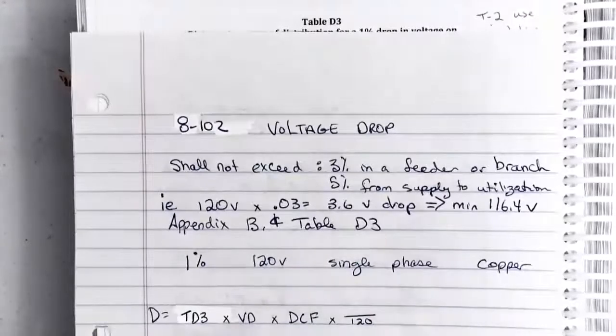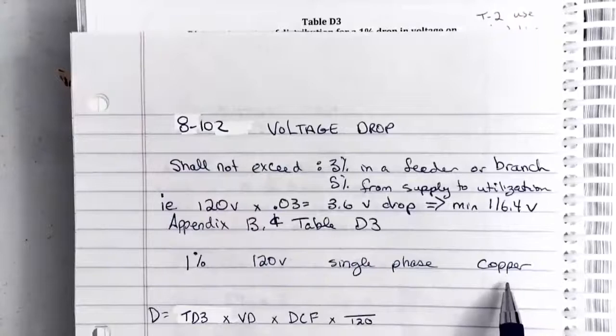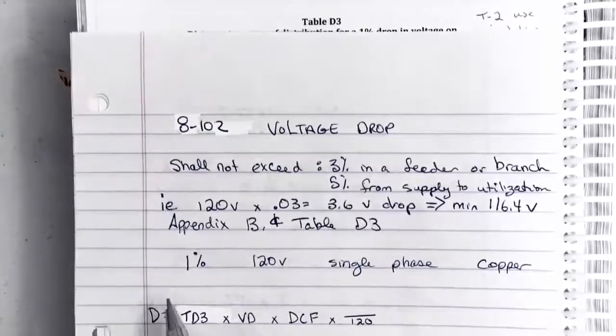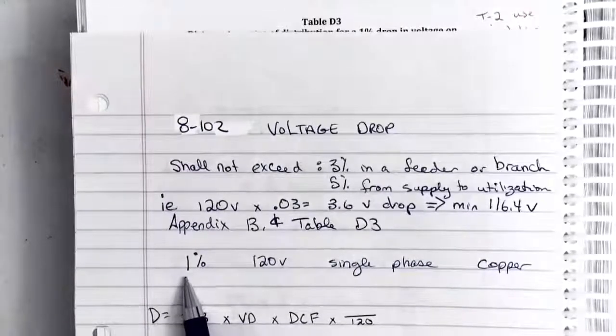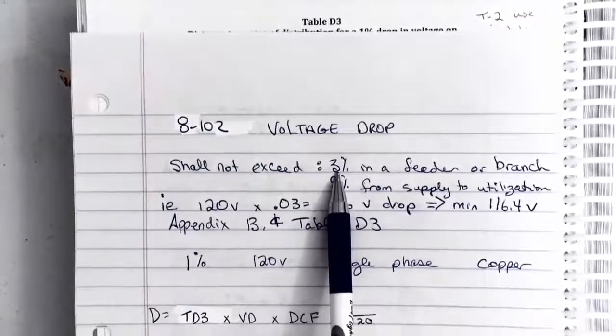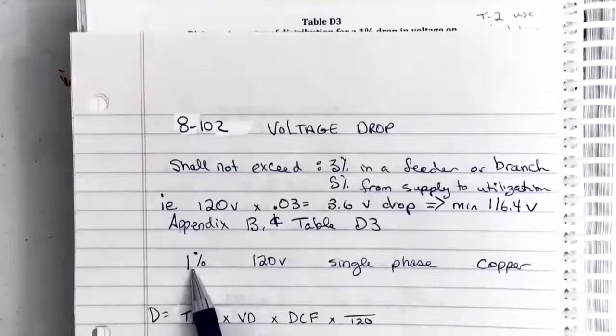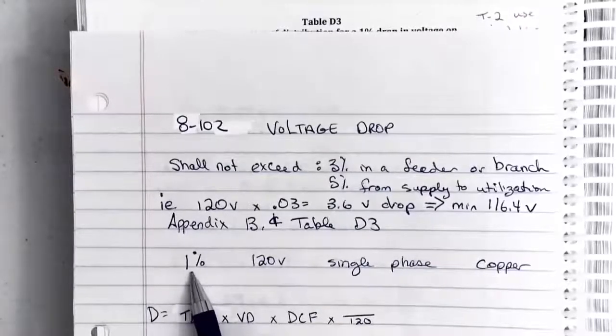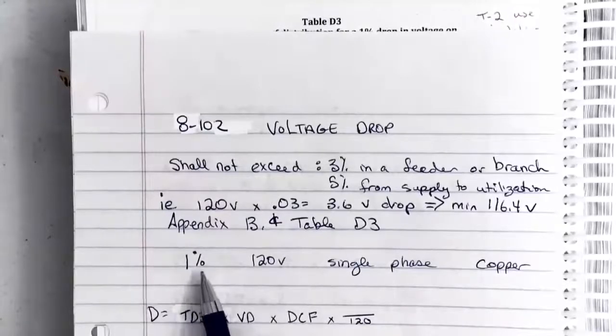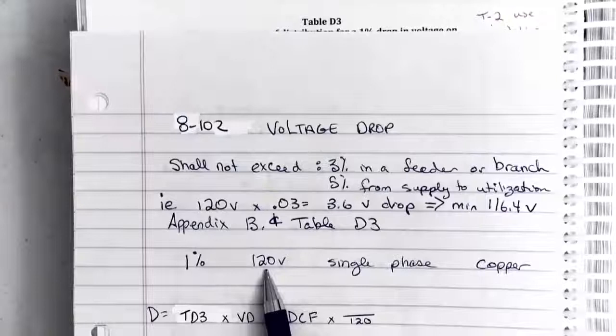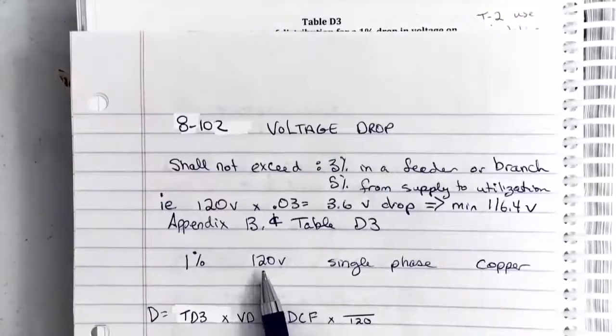Table D3, if you notice, these values are written down here: 1%, 120 volts, single phase and copper. Now these are the parameters that Table D3 was designed and built around, and so sometimes we'll end up adjusting for these numbers. For example, if we're in a branch circuit and we're looking for a maximum of 3% and the table was built for 1%, we're going to replace that part of the formula with 3% instead of 1%. If the voltage of the circuit that we're actually trying to figure out the voltage drop in is more than 120 volts, we're going to have to adjust this formula to match the voltage in our actual circuit.